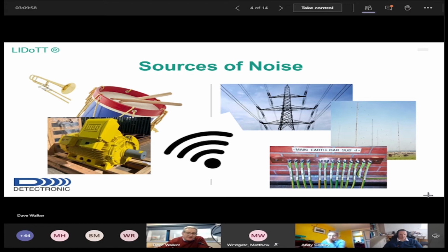Just behind the trees at that treatment plant, there's a row of dense trees, and there was a radio transmitter. And that's what was happening: the radio transmitter was transmitting the noise onto the perimeter fence, bringing that noise to our instrument. And in this case, it was bringing it back up through the earth supply. So it wasn't even radiating onto the actual instrument itself. On that, we have advanced over the years, and I'll touch on how we now eliminate some of that noise.